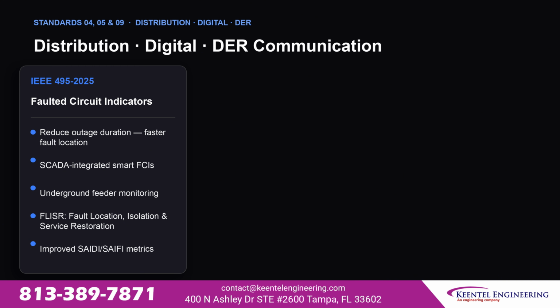IEEE 495-2025 updates faulted circuit indicators. Smart FCIs integrated with SCADA cut outage restoration time significantly, with the 2025 edition adding SCADA communication requirements and FLISR support, fault location, isolation, and service restoration. Better SAIDI and SAIFI metrics are the direct result.